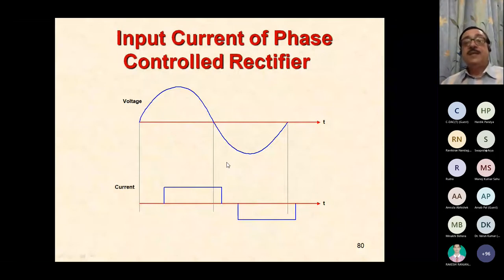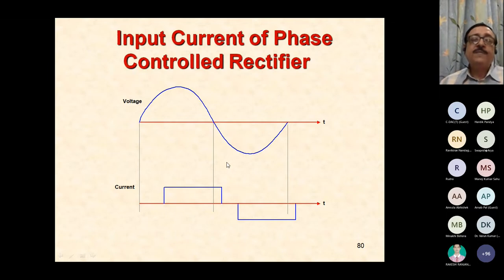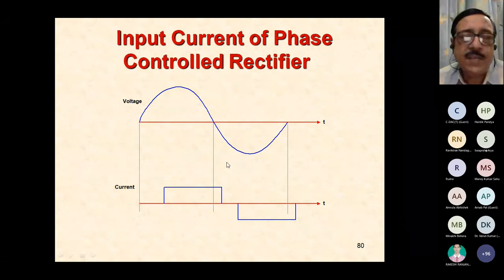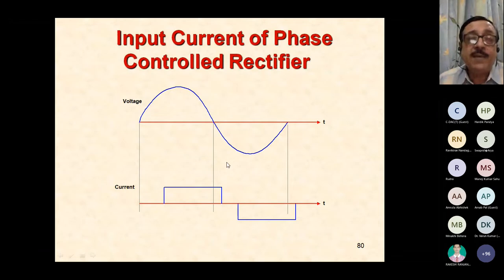So therefore, in case of phase control rectifier inputs, the power factor is going to be one of the worst, and it's going to vary depending on the firing angle utilized. So therefore, phase control rectifiers are being slowly phased out of operation for anything below 10 kilowatts of power, and switch mode converters are taking over. Phase control rectifiers are still existing in large power ratings because of their reliability in large power applications, but certain techniques are involved to make the power factor close to unity. You cannot make it unity, it's close to unity, and reduce the current distortions.